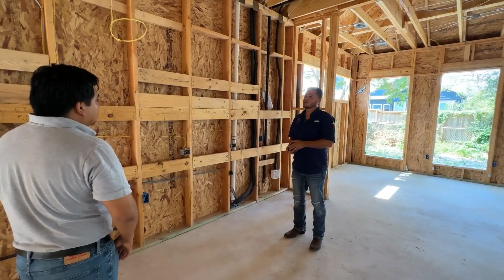So what's your process after that? After we have the vent hood here, you connect it yourself - I know you've done that many times. Pretty much the guys that provide the vent hood or appliances are the ones who install the vent hood, then we come and do the connections per the Code of Austin. It has to have foil tape around it and some duct sealant as well, and then we put the pressure switch or sensor to the makeup air kit.